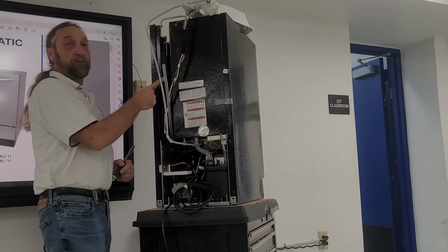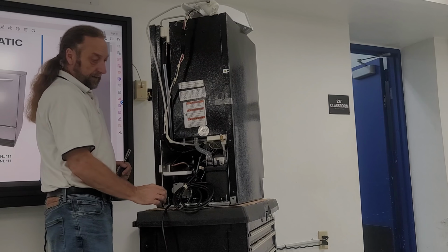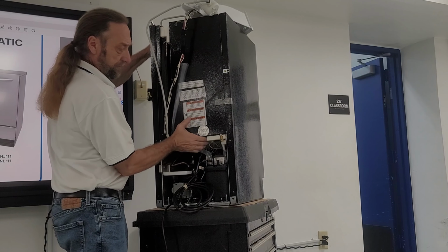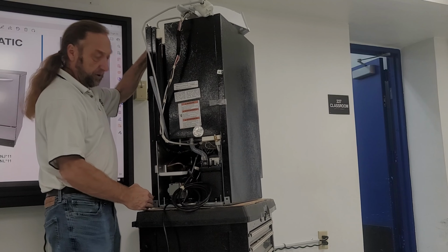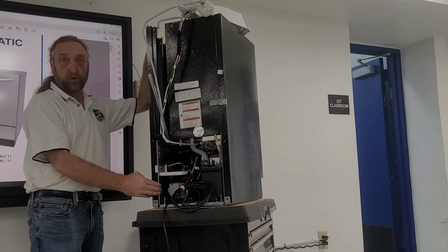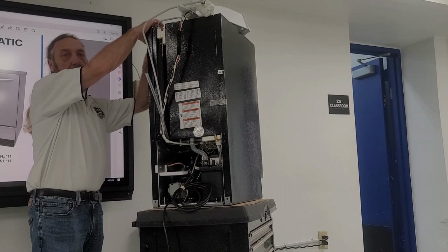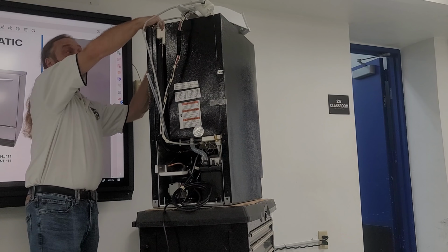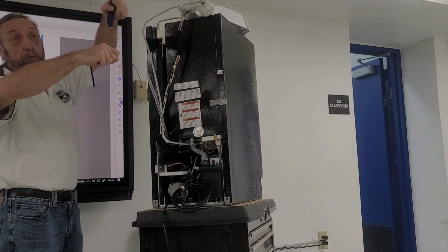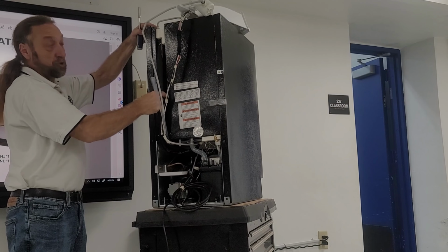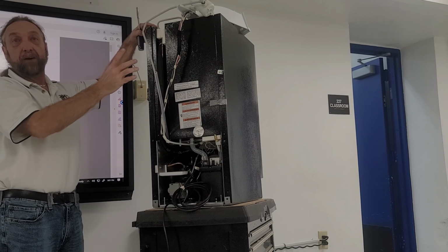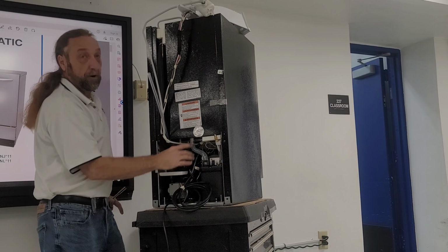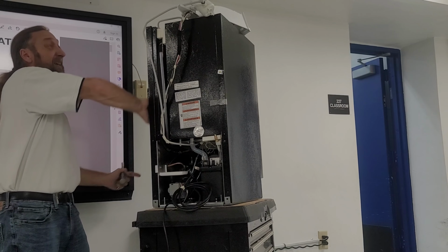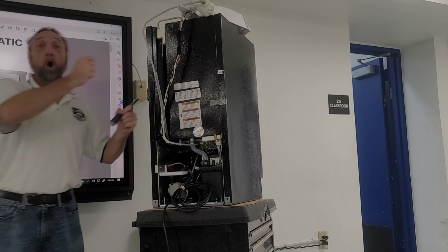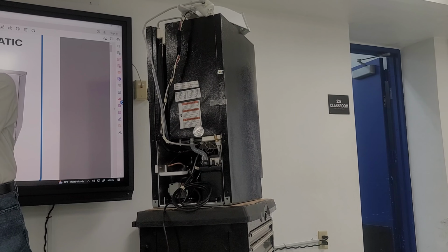Now remember I said these refrigerant lines run here. This piece will lift up off the back, and you put a little 2x4 underneath there. In the video it shows you, but it's better to take the evaporator loose with screws and bring it over the back, since these lines are just loose here. Now that the evaporator's out of the way, with the compressor, condenser, and evaporator accessible, you can take this entire cover off and out of the way for service.